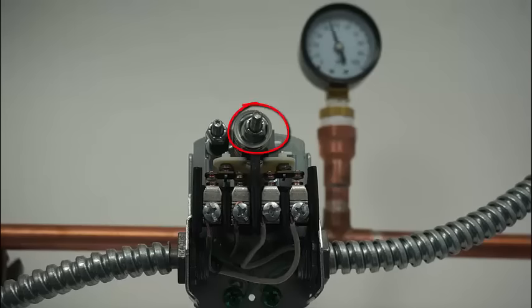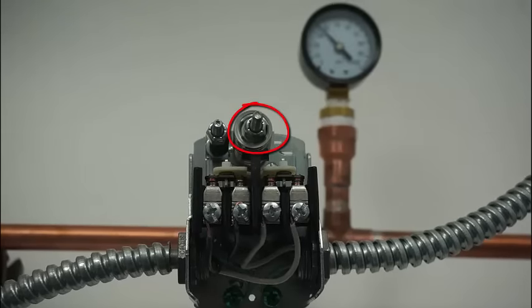You can increase the high pressure set point by adjusting the large nut clockwise. One turn increases the set point by approximately 2.5 PSI.